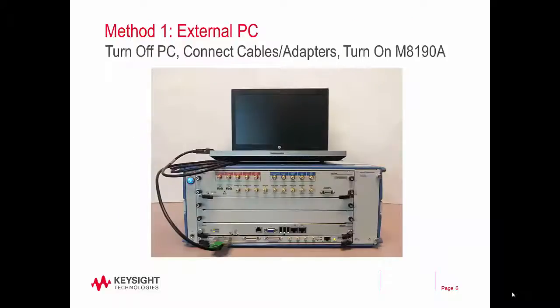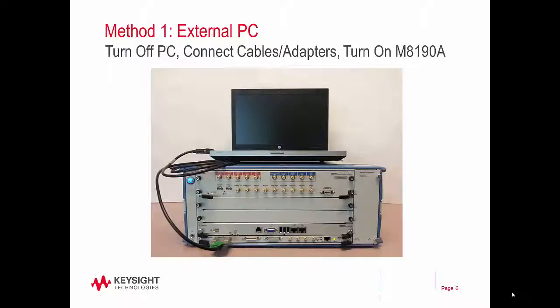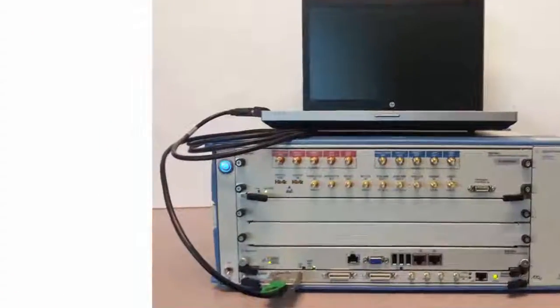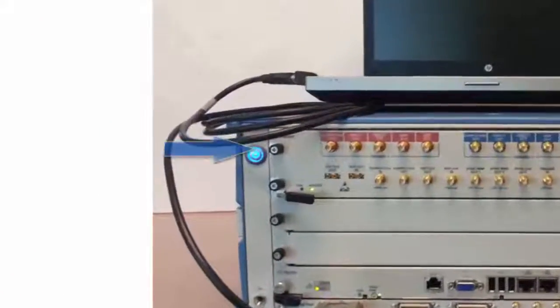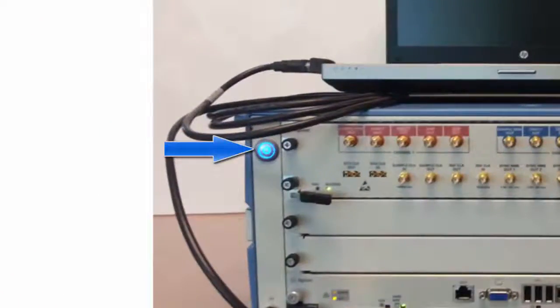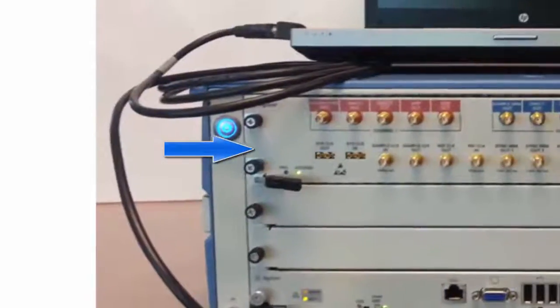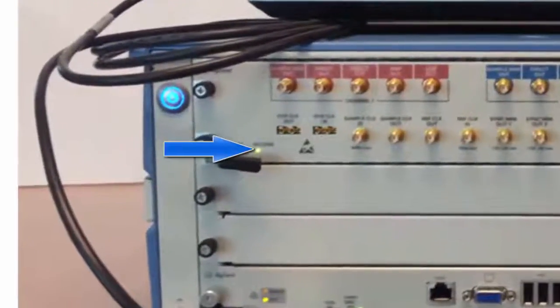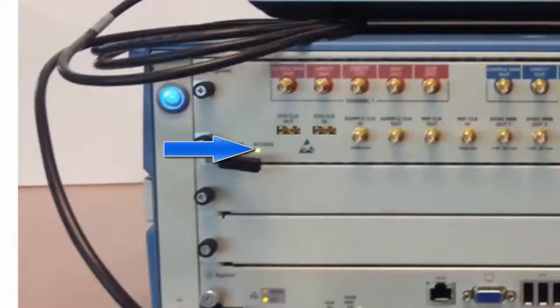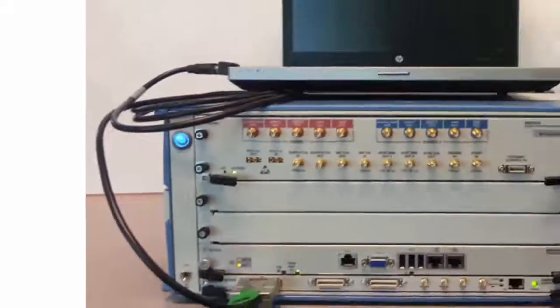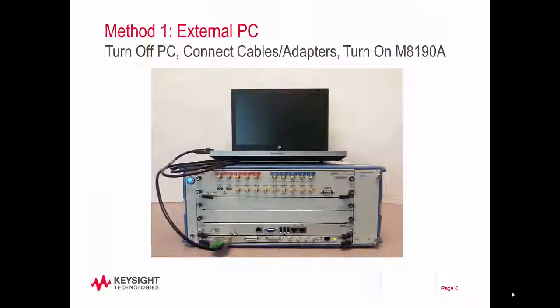Once the software packages have been loaded, and when you are using an external PC, you will want to turn off the PC and connect the appropriate PCIe cable and adapter to the PC. Once those are connected, turn on the M8190A by pressing the power button in the upper left corner of the chassis. There is an LED on the M8190A labeled Access. Wait until it turns to green before turning on your PC. If you are using the embedded controller, simply turn on the power to the whole chassis.